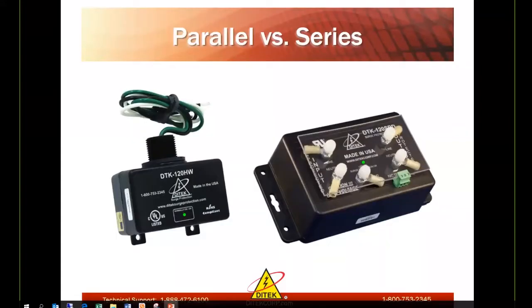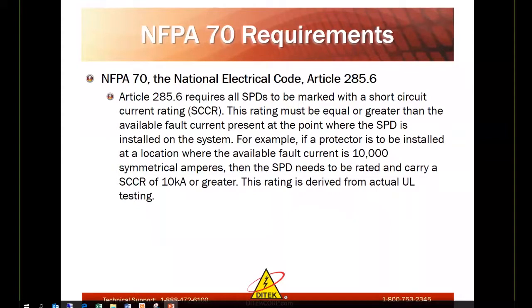Parallel versus series, we touched base on the 120HW as well as the 120SRD. Those are the two devices featured there. NFPA 70 requirements are in the National Electric Code. Article 285.6 requires all SPDs to be marked with a short circuit current rating, which we call SCCR.